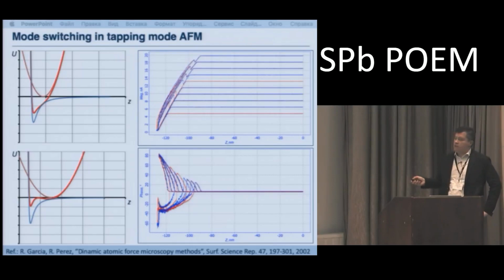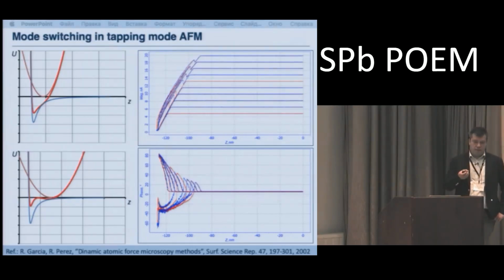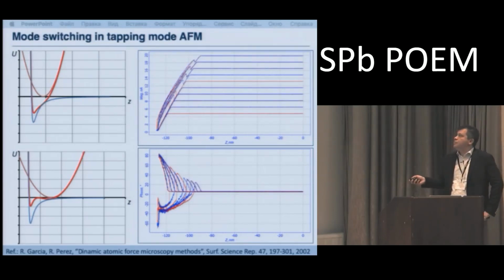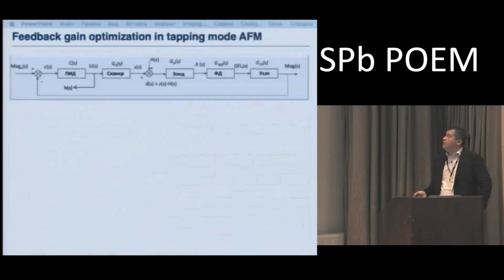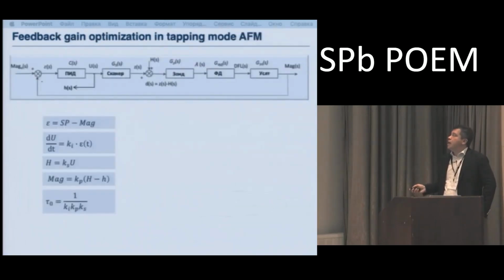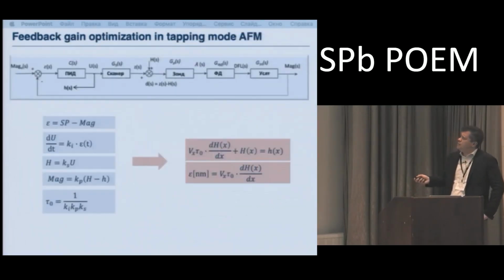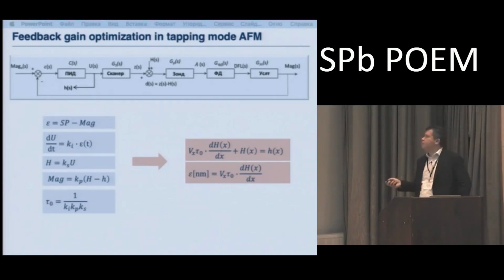And the phase of the cantilever oscillations is a good signal, and the system itself, it might be problematic for the operator to control it, but for the system itself, it's not a problem to control the phase of cantilever oscillations to understand if it is in attraction or repulsion regime.